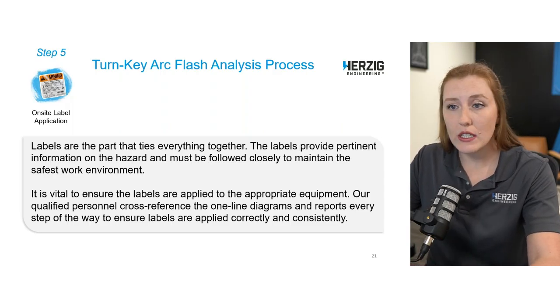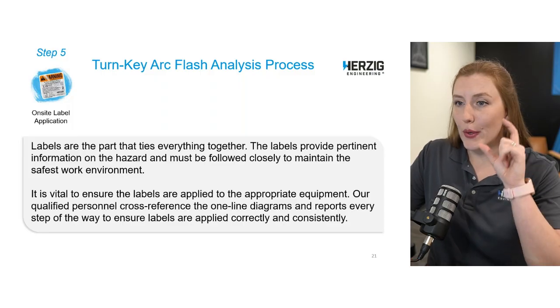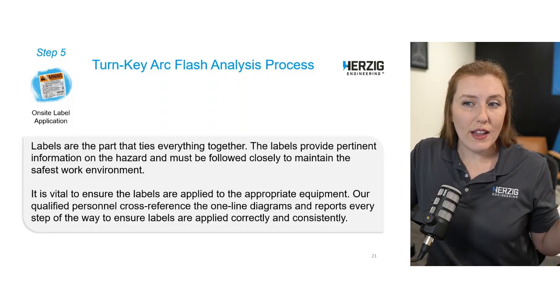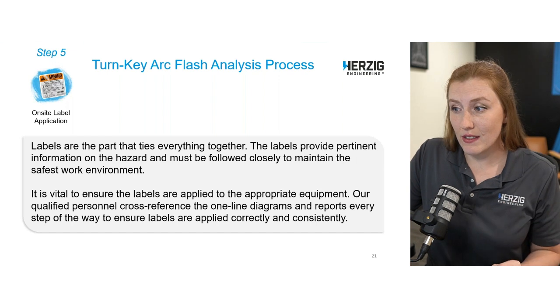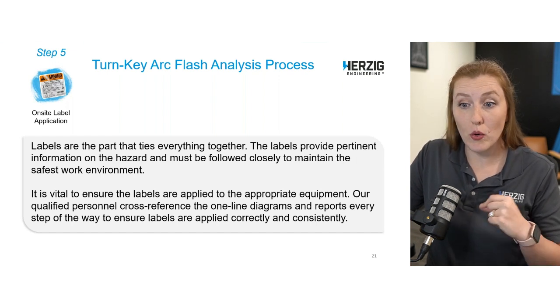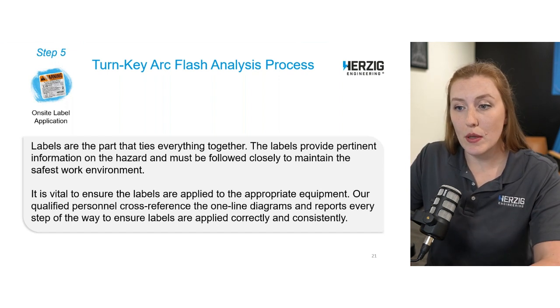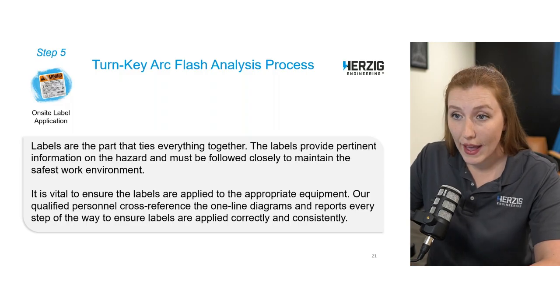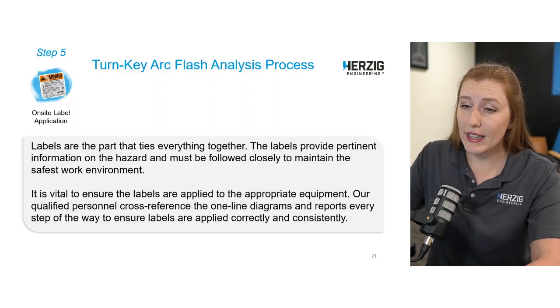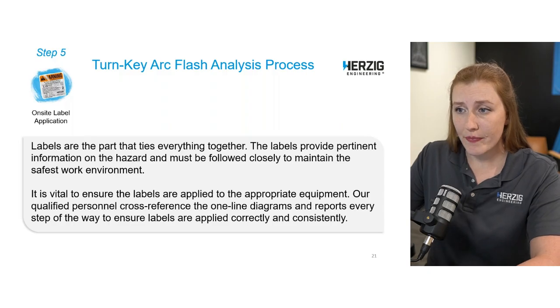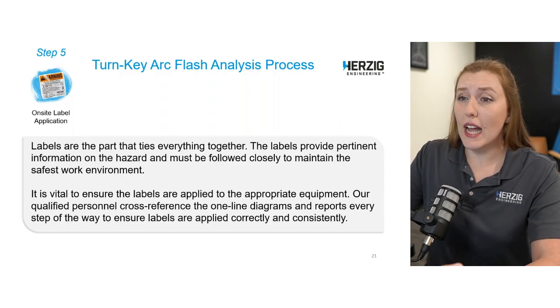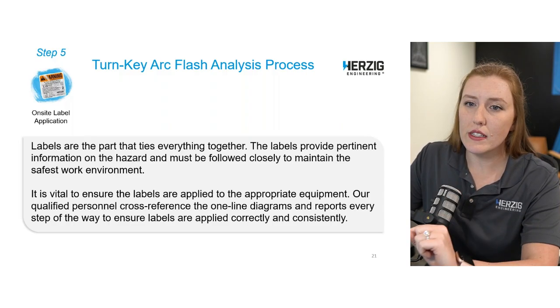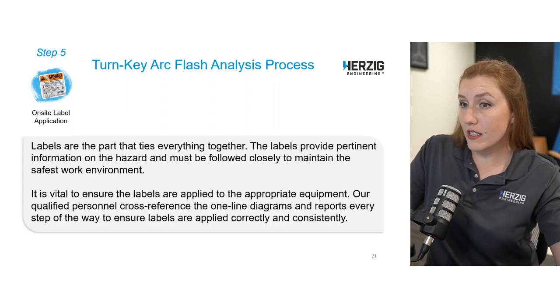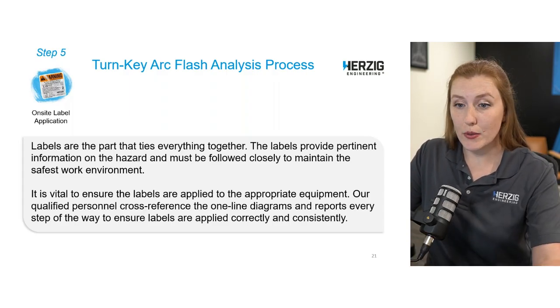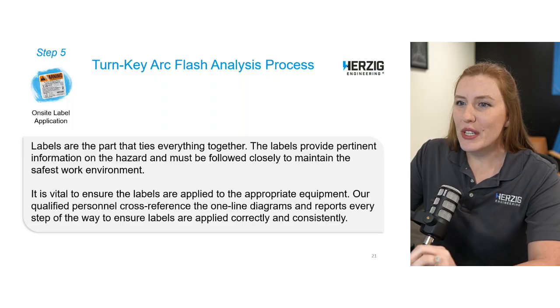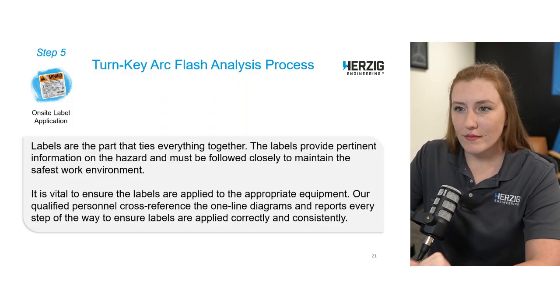The last thing we want is to accidentally put a label for a lower arc flash hazard than what's actually present on that equipment. So we cross-reference with the one-line diagram and reports every step of the way to make sure that they're being applied correctly and consistently. This is kind of a big deal. So whenever I talk about this for engineer-assisted versions, where maybe you guys are going to be doing this, I'm going to have some pretty specific emphasis on this.